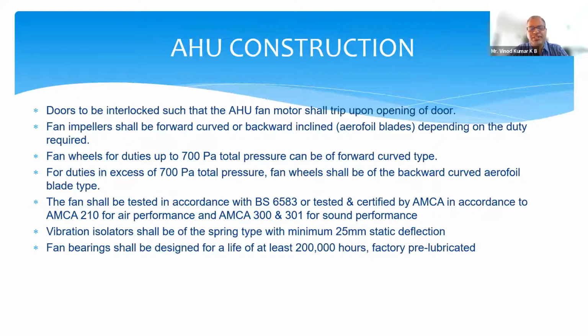So you can imagine the kind of pressure the hospital will go through because you have a problem with the AHU. So this fan again, not only the type of fan is important, the fans are generally tested for BS standards or AMCA standards. BS standards are basically the British standards and AMCA is basically the American standards for the air performance of these fans or impellers or for the total sound performance. It's important.